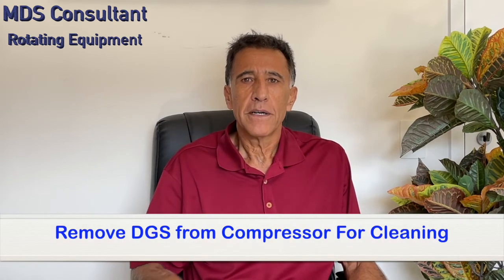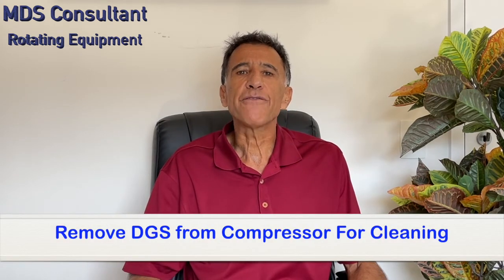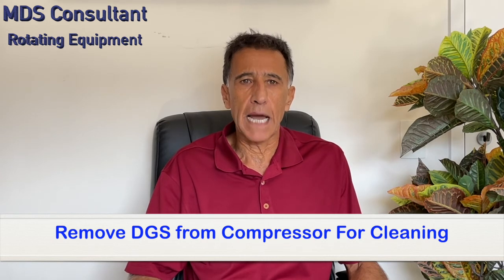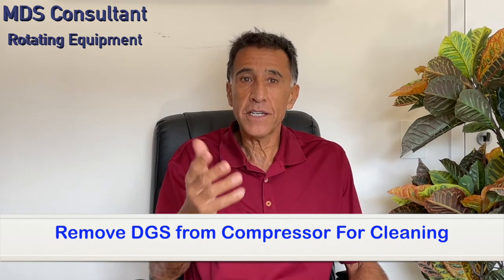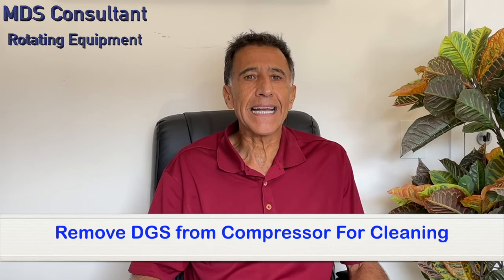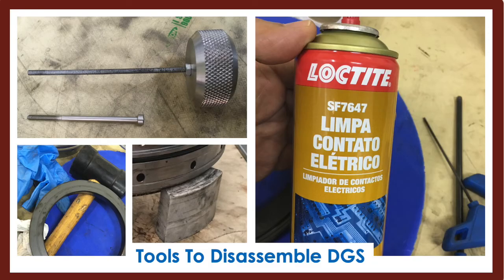Okay, alcohol flushing didn't dislodge the seal. Now what? Call OEM? Not so fast. Most of you guys have tooling to remove the seal, right? Get the booger out and have a good look. And if there is no obvious sign of mechanical damage or fractures, then take it somewhere nice and clean to open it up. All you would need is a few Allen keys, a few long screws, a few soft blocks, and a soft hammer to take it apart.